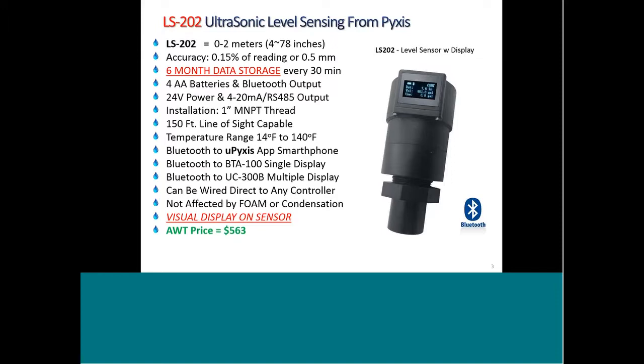Another functionality in the Bluetooth mode is some customers like to still connect it to their controller. So we offer a single channel receiver called a BTA100, which can be wired into any controller and takes that Bluetooth inventory signal, wirelessly receives it from the device, redisplays it, and then converts it for a wired input to a conventional controller. So there's a lot of functionality built into this technology above and beyond a conventional ultrasonic meter that you would hardwire.